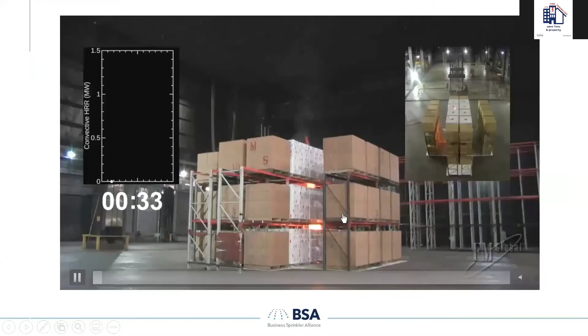We're just coming up to a minute into the fire since ignition. You can see the fire is already out of the top of the storage array. The view in the top right looks backwards over the array, and on the left is the heat release curve measured at the ceiling. You can see how, over time, it's rapidly going up, and nothing is stopping it.